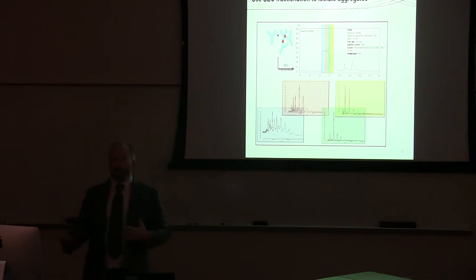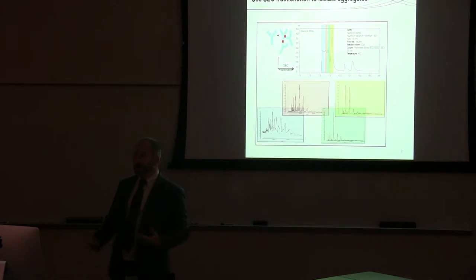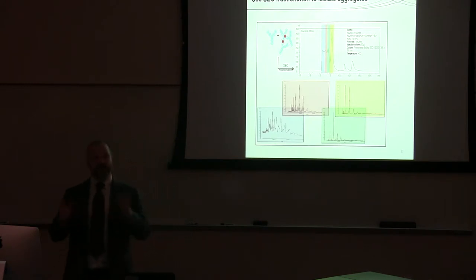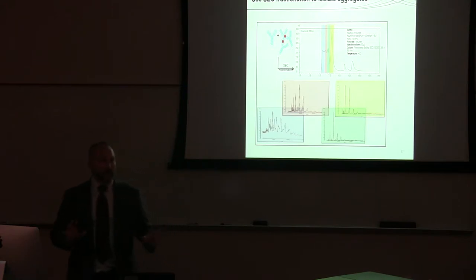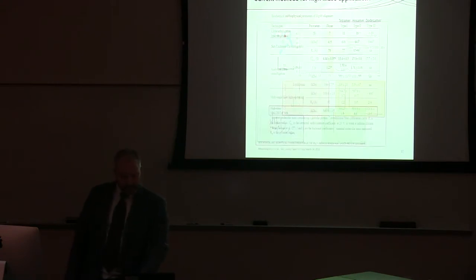You can take it a step further, and you can do offline separation. So, this can be orthogonal to GPC analysis. So, you can do the GPC fractionation, collect the fractions, and then analyze for these aggregates. And that might give you a little bit more sensitivity towards the higher end of things.